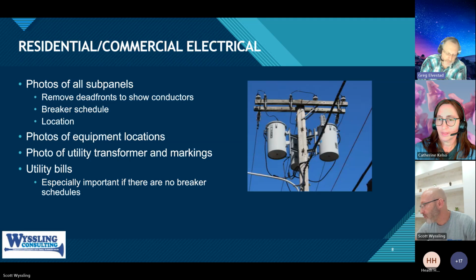This is helpful in making sure, number one, can we put as much PV on this property as you're trying to do? Sometimes the service may be undersized. Dirty little secret, because I used to be a power company engineer—you're not going to find a 3,000 amp service with a 3,000 amp rated transformer.